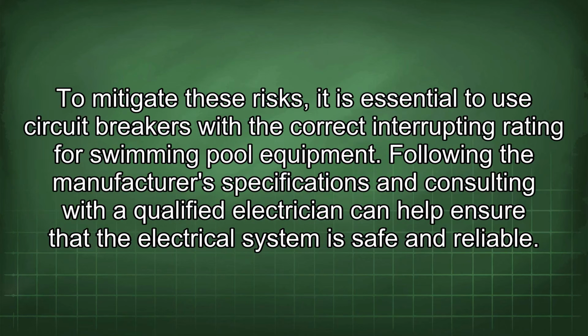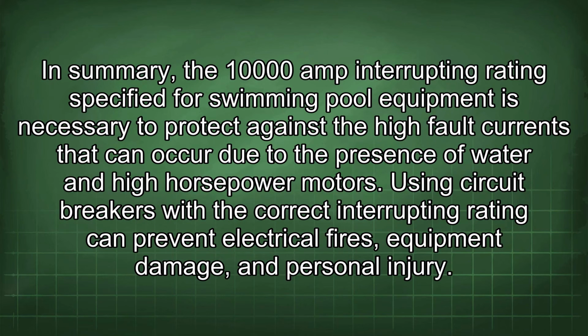To mitigate these risks, it is essential to use circuit breakers with the correct interrupting rating for swimming pool equipment. Following the manufacturer's specifications and consulting with a qualified electrician can help ensure that the electrical system is safe and reliable. In summary, the 10,000 amp interrupting rating specified for swimming pool equipment is necessary to protect against the high fault currents that can occur due to the presence of water and high horsepower motors. Using circuit breakers with the correct interrupting rating can prevent electrical fires, equipment damage, and personal injury.